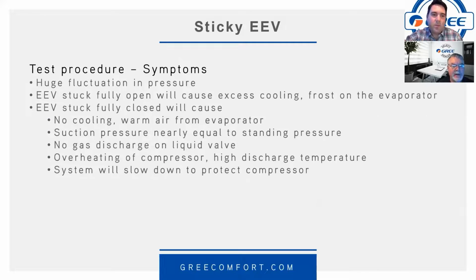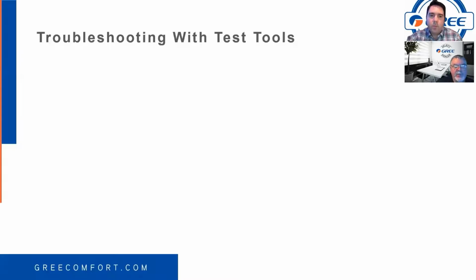And then, what about a sticky EEV? You can have huge fluctuations in pressure. Stuck fully open could cause excess cooling, frost on the evaporator. Stuck fully closed can cause no cooling, warm air in the evaporator, suction pressure nearly equal to standing pressure. No gas discharge on the liquid valve, overheating in the compressor, high discharge temperature. There's our E1. Systems will slow down to protect the compressor, though, at least.